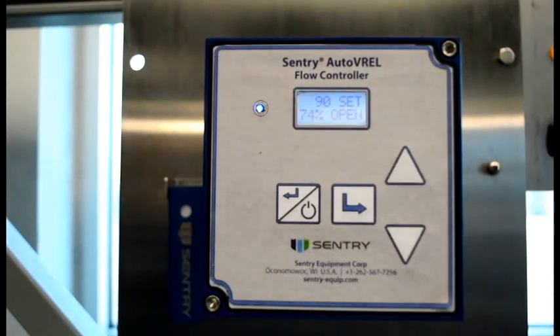Should you experience a thermal event that triggers the TSV, the AutoVREL will respond by closing the VREL to a safe closed position, activating the DCS alarm, and displaying TSV error. The AutoVREL closes for operator safety so that when the TSV is reset, the operator is not exposed to the sample full pressure, flows, and temperature.